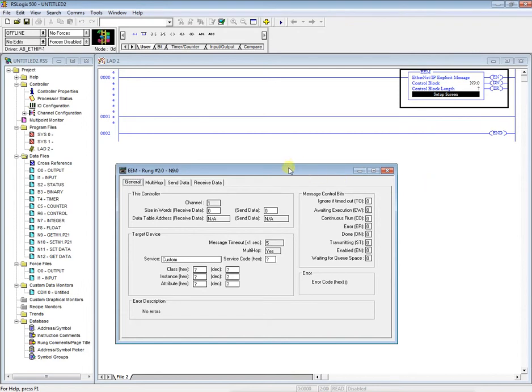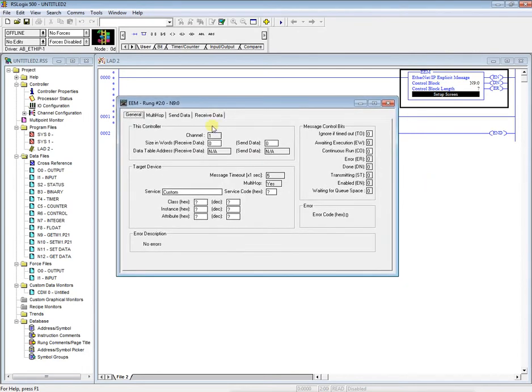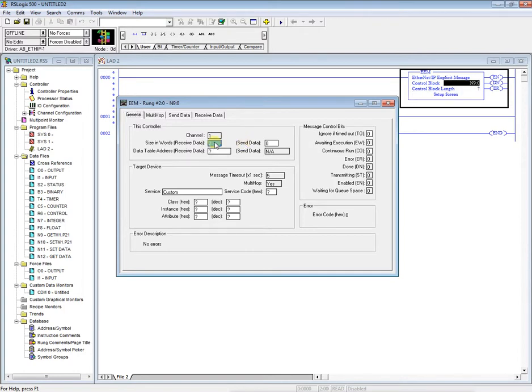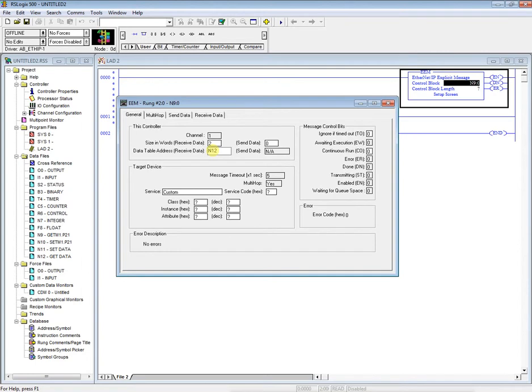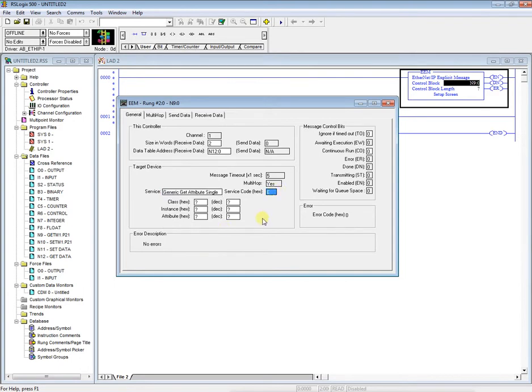So now our properties box comes up for the EEM instruction. Since we're doing the get, we're going to change the words received. So right here we're going to make this two. We're going to send over two words. Where are those words? Where do you want to store those words? So that will be the N12 colon zero. Down here in the service, we're going to change this to the git attribute, generic git attribute single. It'll automatically create this hex code over here.